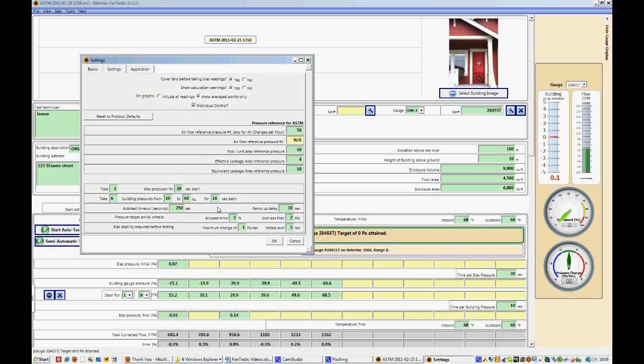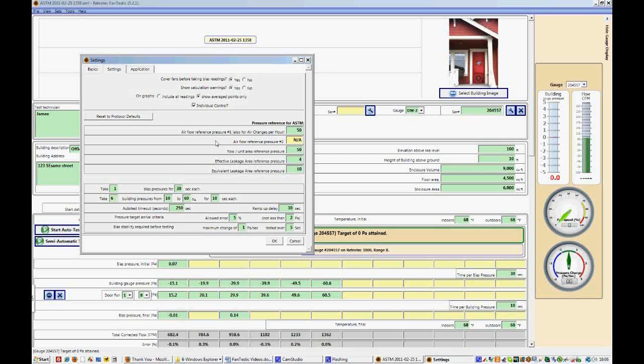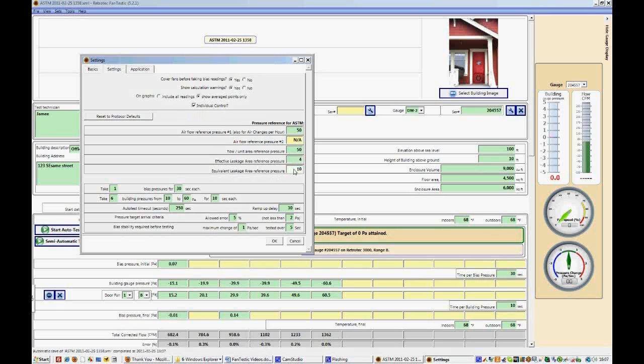ASTM requires you to either go in 5 pascal increments, or 10 pascal increments, or somewhere in between, between 10 and 60. So if you're doing 5 pascal increments, that would result in taking 11 building pressure measurements instead of 6. This is something that can be changed. If you're interested in finding different reference pressures, so let's say air flow at 75 pascals instead of air flow at 50, which it's defaulted to, you can change that here. This also works for air changes per hour. Effective and equivalent leakage areas have reference pressures of 4 and 10, respectively. You can change these in this menu as well.